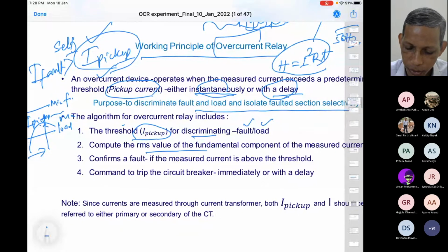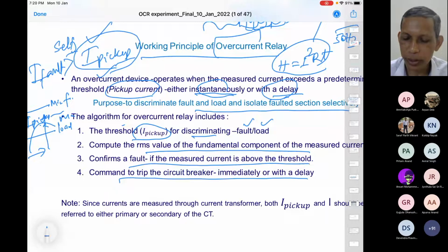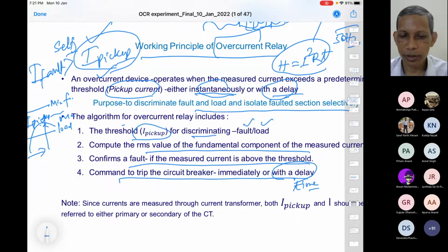Compute the RMS value of the fundamental component. The relay confirms a fault if the measured current is above the threshold. The trip command is issued with a delay or without a delay. When you talk about a delay, to have flexibility in the system in a selective way, we are talking about introducing time into the decision process. How much time? You can ask, how much time?